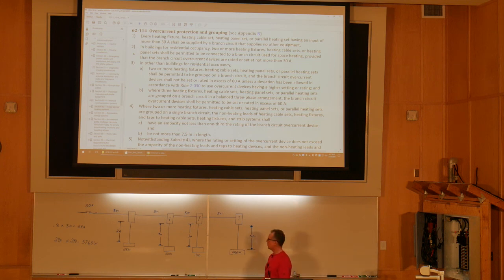So 62-114 is going to be our example here, subrule 2. And these are going to be thermostats and baseboard heaters. So we'll carry on with the rule. 62-114, subrule 2 is the one we're going to apply. Then we're down to subrule 3. In other than buildings for residential occupancy. So subrule 2 is the residential occupancy, and subrule 3 is everywhere else.